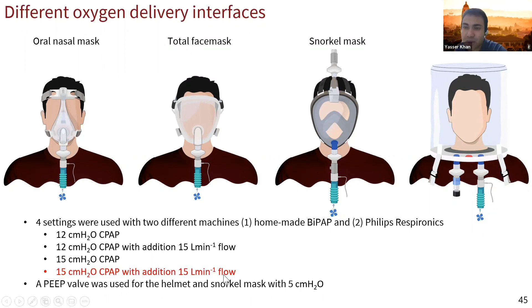And what we saw is we were basically trying to figure out what's the best setting to run the tool. With 15 centimeter water pressure and 15 liter per minute oxygen flow, we were able to generate a good PEEP. Okay, so this is the helmet with 15 centimeter CPAP pressure, room air, and now we are mixing that with a 15 liter per minute oxygen flow. So it's essentially the same. We don't see much variation from a commercial NIV. Our device works almost similar.